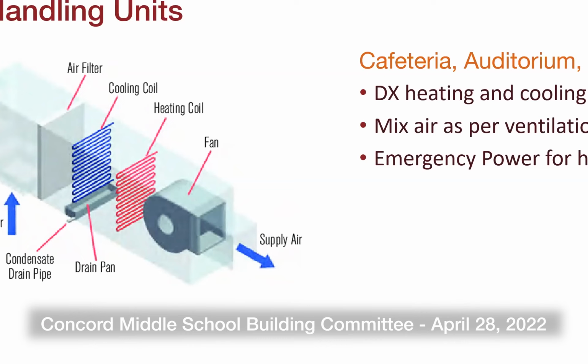These are what's going to be working for the cafeteria, auditorium, and gym. We're going to be doing a DX, a refrigerant-based system for heating and cooling. We're going to be using mixed air in these spaces because they have fairly high ventilation requirements that are also closer to their heating and cooling requirements, which makes air handling units a great choice. They'll be on emergency power since they're providing heating to those spaces—not due to life safety, but due to freeze protection for the sprinkler heads. So that's the air handling units.